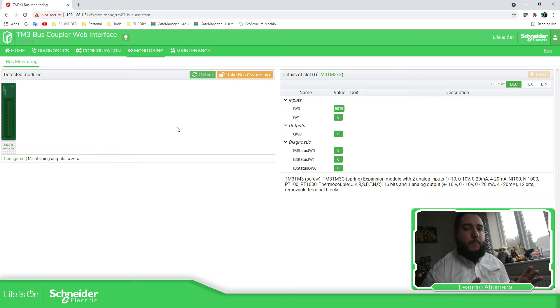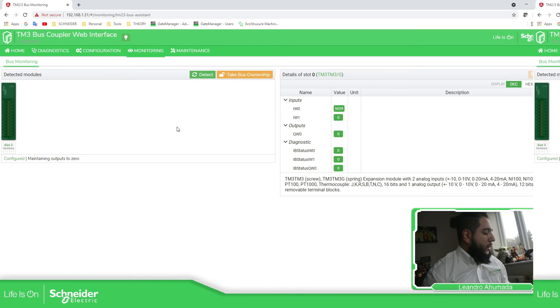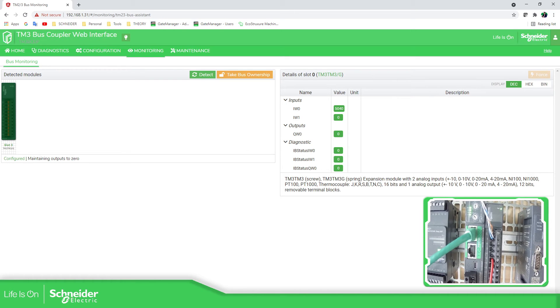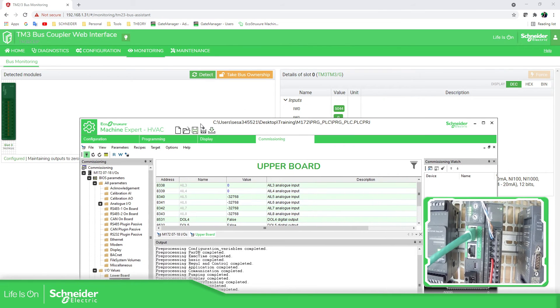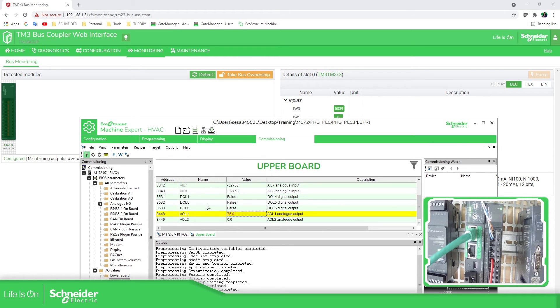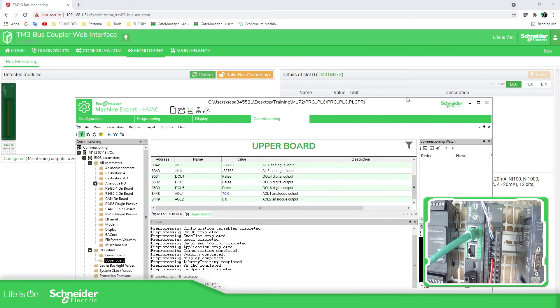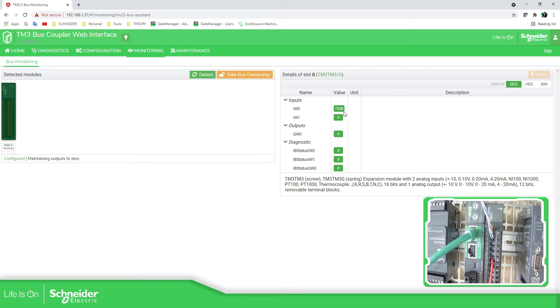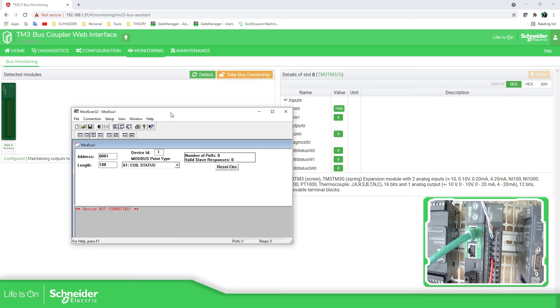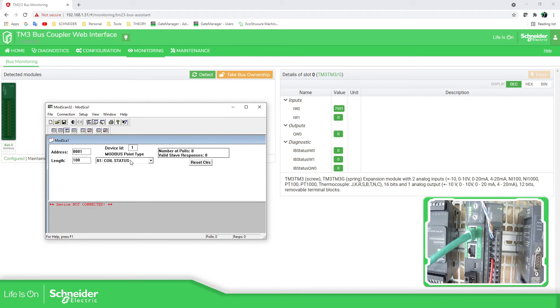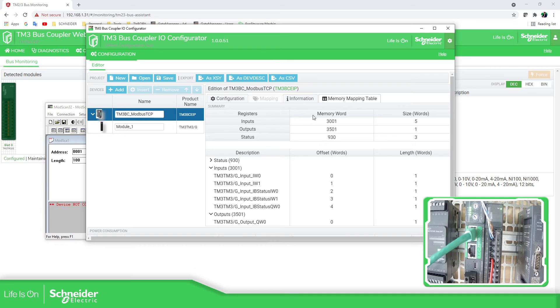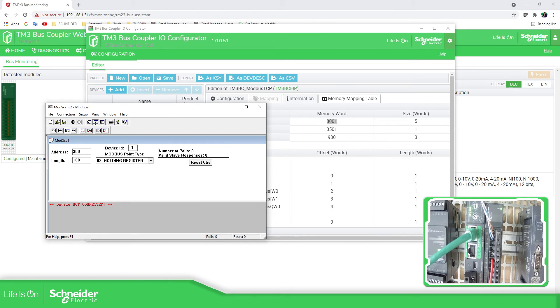Here you can see I'm sending information from the other PLC to the bus coupler. If I change this value, you should be able to see data now. Let's change this to 75 — you can see it's changing. Now if you want to use the information from the bus coupler in another device, we can do this using ModScan. We should be able to see holding registers. The length will depend on what we have configured on the bus coupler. If the input register starts at, for example, 3001, that will be my starting address — so 3001.